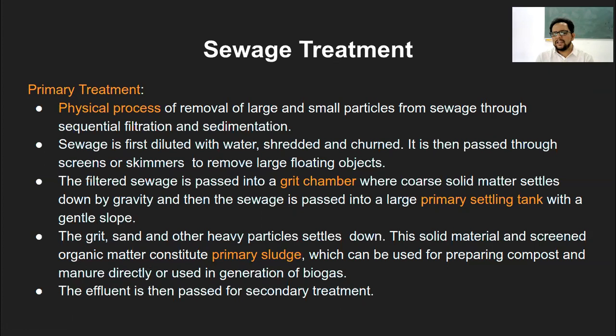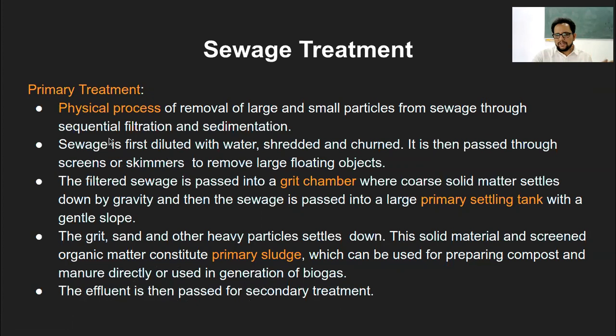Primary sludge is the thick material accumulated as sediment. It can be used for preparing compost, manure, and for generating biogas - since it contains a lot of organic material. The remaining effluent, the top portion of the water, is passed for secondary treatment. So the sequence is: screening first, then grit chamber for sedimentation, then the primary settling tank generating primary sludge, and the sewage effluent is passed for secondary treatment.